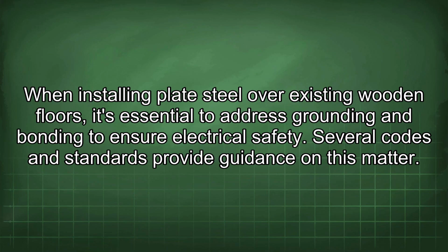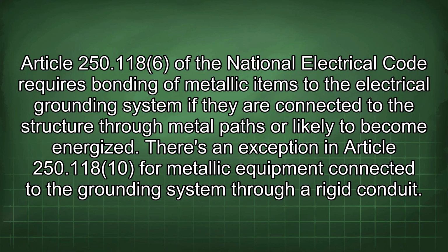When installing plate steel over existing wooden floors, it's essential to address grounding and bonding to ensure electrical safety. Several codes and standards provide guidance on this matter. Article 250.118(6) of the National Electrical Code requires bonding of metallic items to the electrical grounding system if they are connected to the structure through metal paths or likely to become energized.